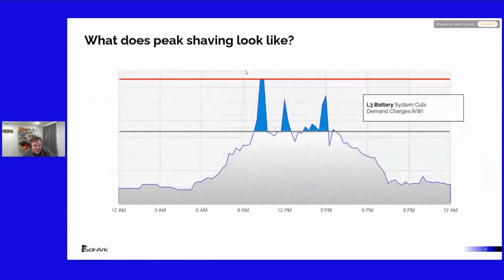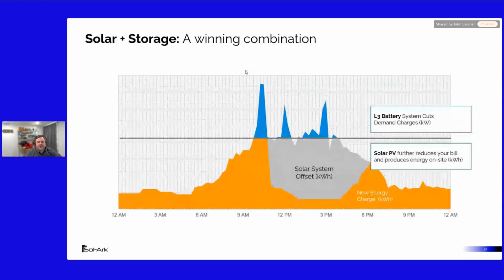What's really interesting about demand charges is they have this reverse economies of scale, where smaller projects are actually more cost effective than bigger ones. As you get further into demand management, you're starting to get into base load, and you'd need a battery ten times the size to achieve the same amount of bill reduction. Solar can sometimes accentuate these peaks, though you'd have to be in a very sunny climate like California for this strategy to be relied upon.